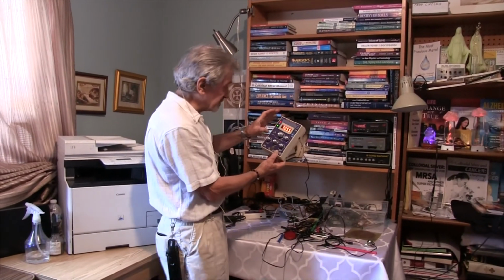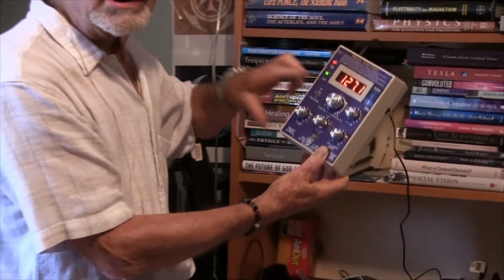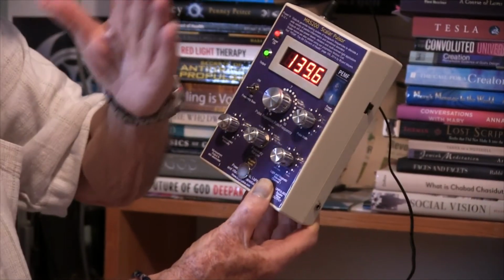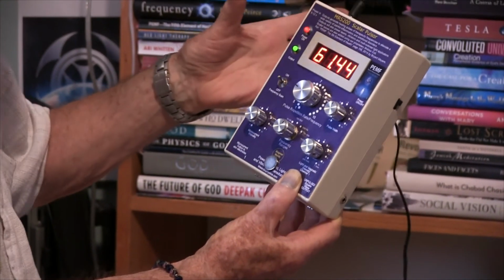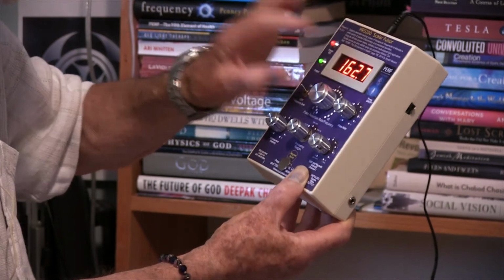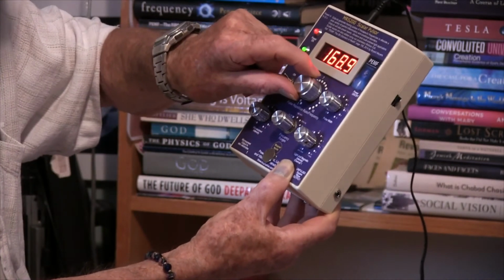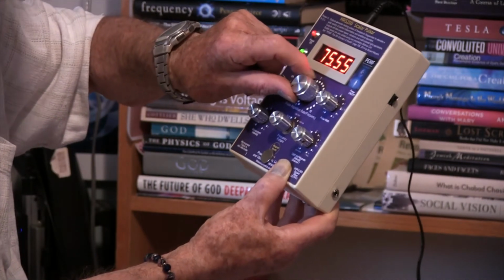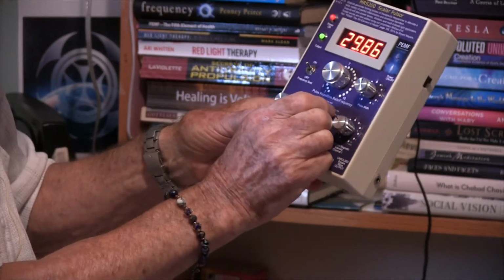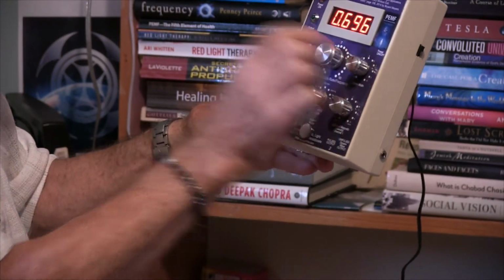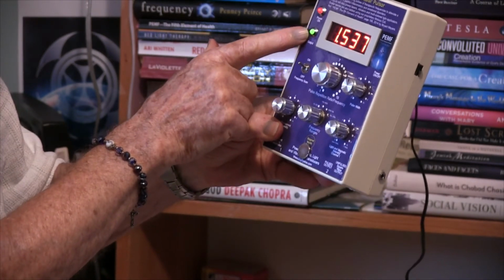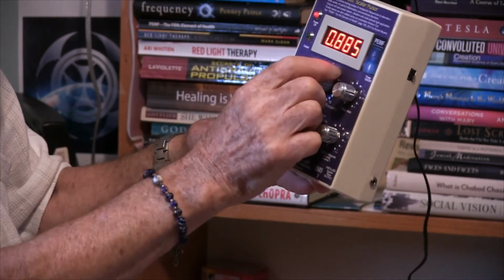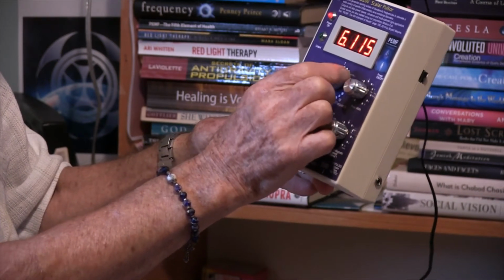So just recapping the front panel, this is the on-off for scanning. This frequency scans back and forth and is actually more effective than having it at a fixed rate. This is the linear analog frequency control. This ranges from the lowest range, which is about 1 per second. And this little light indicates what the master oscillator is doing.